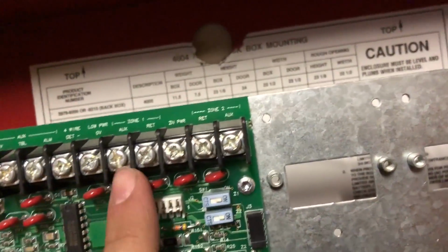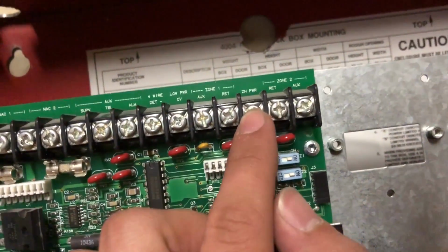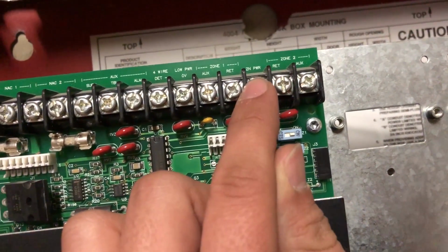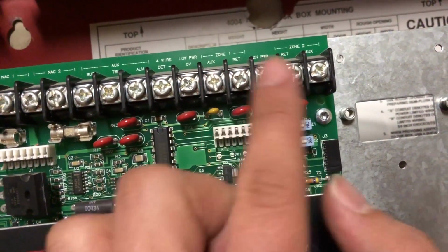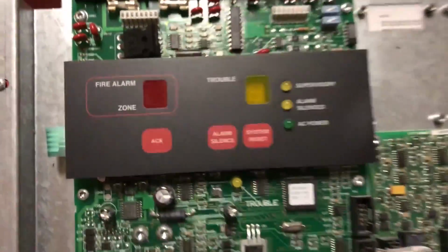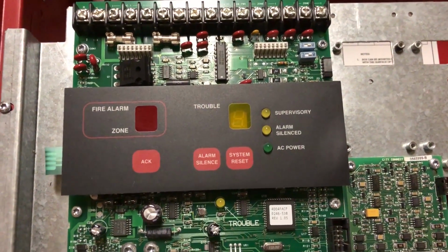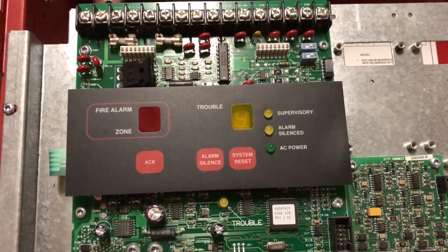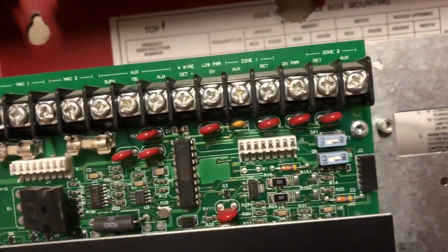Now the zones is otherwise known as the initiating device circuit. In this case, this one's a little interesting because this panel has a shared positive and the negatives are different. And then they also have auxiliary negatives, and I don't really know the details on how that works with this panel. This panel is older. It's a little different. I don't necessarily see an assembled on date exactly right here in front of me as of right now, but I'll try to find out in another video, going over this panel specifically.